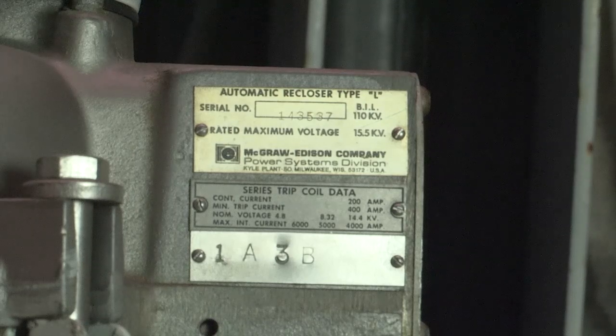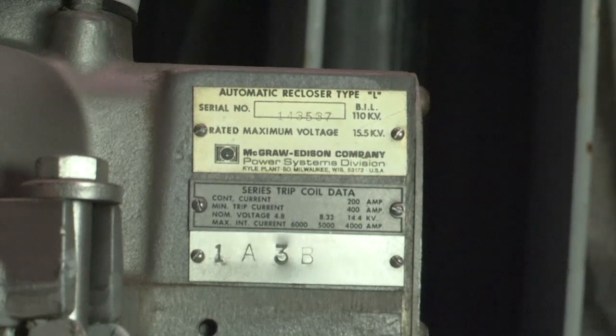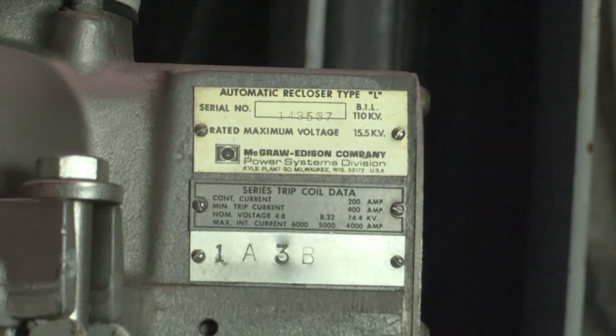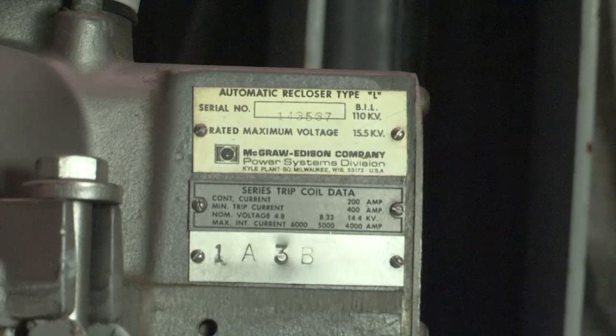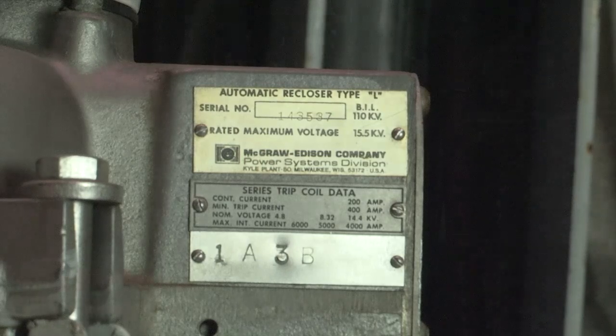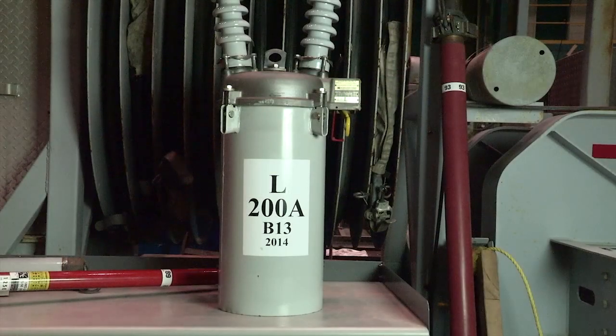Now if that tree branch is still there, the recloser will do its first fast trip. The fault is still there. Now we'll do 3 more delay curves, which is the B curve. So it takes a little bit more time, and it'll reclose 3 times to see if that fault is still there or not. And if it is still there, then the recloser will trip and lock out, and that person will be out of power.